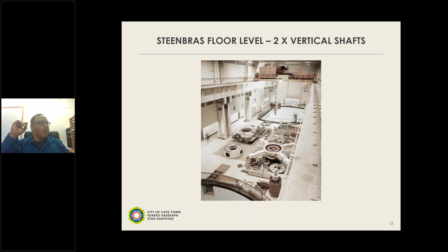The heaviest part of our plant down there is the rotor pole in the middle, coming in at about 40-45 tons. Each of the 10 poles around it weighs about 2.2 tons, so in total you're looking at about 60 to 70 tons that need to be lifted. Normally we remove the rotor poles and lift them out individually. As long as I've been here, we've never lifted out the entire rotor, only portions of it.